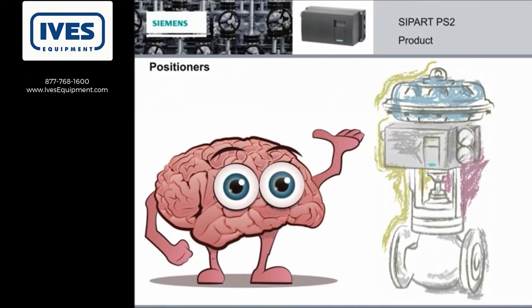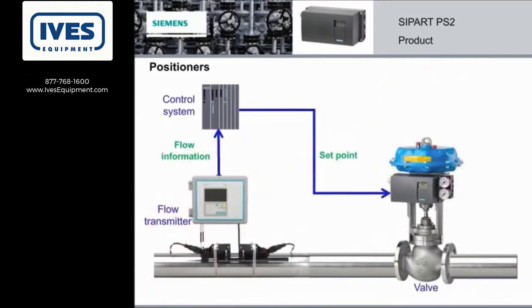The positioner is the brains of the system, and it controls the actuator. Here's how it works: the positioner receives the set point, detects the valve position, and then changes the compressed air supply of the actuator in order to drive the valve to the requested set point.